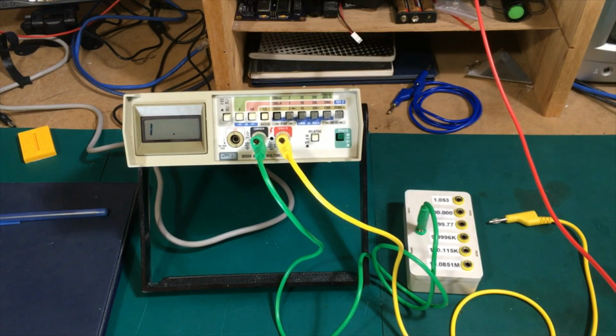Okay, we're not going to be doing a calibration adjustment here. We're just going to look at whether or not the meter needs calibration, or is it fit for use as is. A couple of things should be considered in doing this. First, my use of this will never involve higher voltages, so I'm not concerned about the accuracy of the highest ranges. Second, the way these meters work, everything is based upon voltage references and precision dividers.